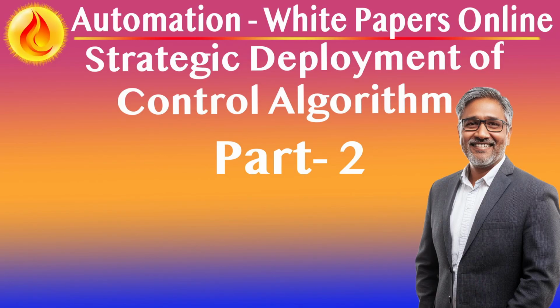Application guidelines for PD control. Ideal for large capacity or integrating processes. In batch operations, level systems, or thermal processes where aggressive offset elimination is unnecessary during transitions, PD offers faster stabilization than PI or PID. Use in set point ramping or predictable transients. When processes exhibit predictable dynamics, the derivative mode preemptively adjusts the output to meet future state demands more effectively.